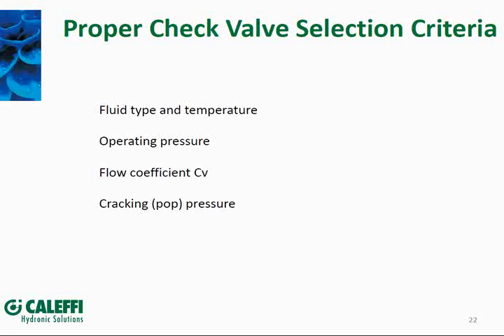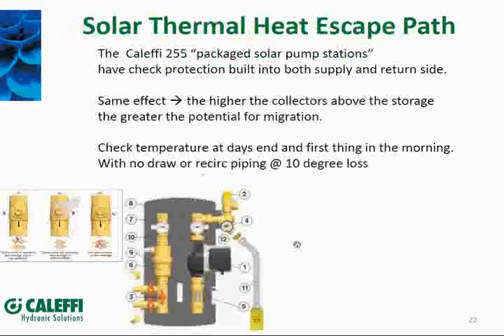The selection process for check valves considers: type of fluid in the system, operating temperature, operating pressure, and critically the CV rating. Make sure the valve isn't oversized — don't use a 28 CV valve when you're only moving 8 GPM, especially with a swing check. Check valves can also be ordered with different pop pressures; for hydronic applications, typically about 0.25 psi is standard, which is low enough for even the smallest pumps to open.